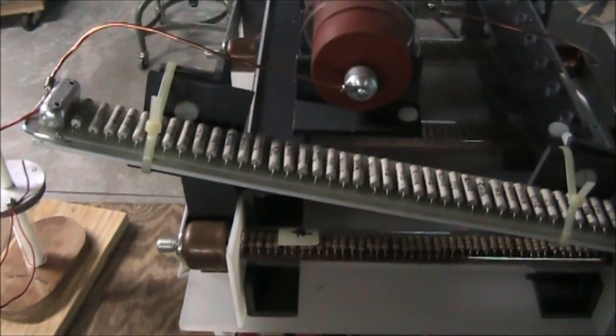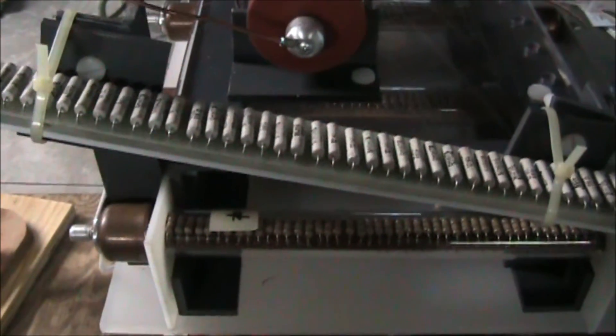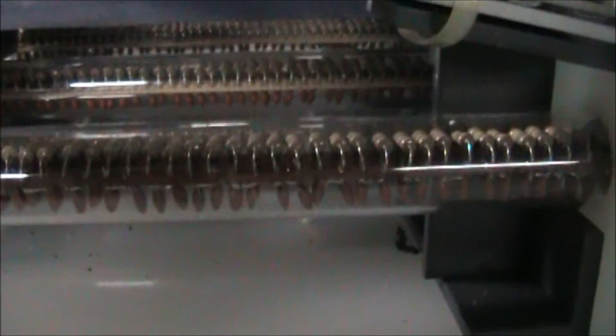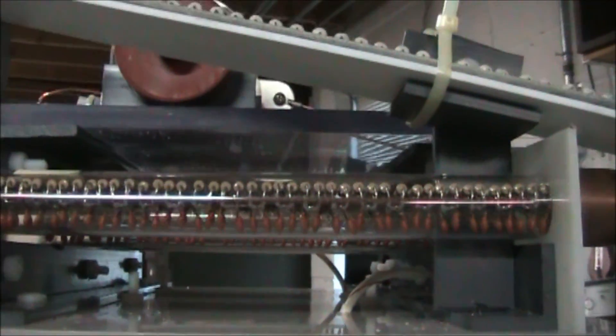I just want to point out as I conclude this video this unit is full of bleeder resistors besides the charging resistors. I have the equalizing resistors all across the diode assemblies. I mean this whole unit has a couple of hundred resistors on it as well as equalizing capacitors so there is a lot of bleed down on this system which does enhance its safety.